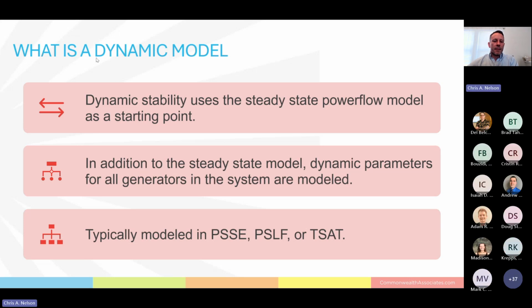It needs to pump out a few more VARs to raise the voltage or negative VARs to lower it. So what is a dynamic model? To start with, we have a steady state power flow model, usually in PSSE, PSLF, or some other programs. But a dynamic model builds on that and creates basically generator parameters.